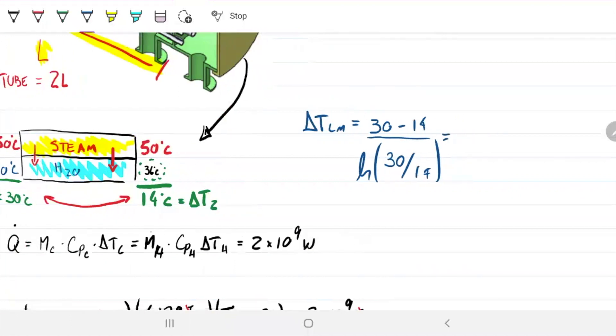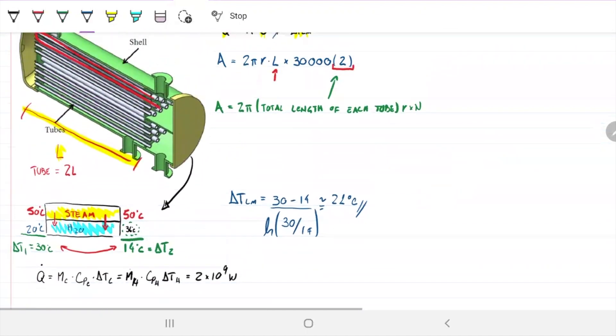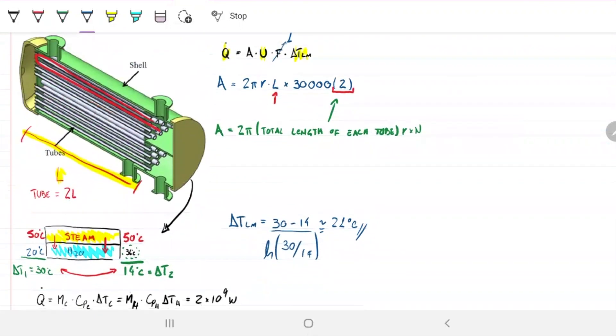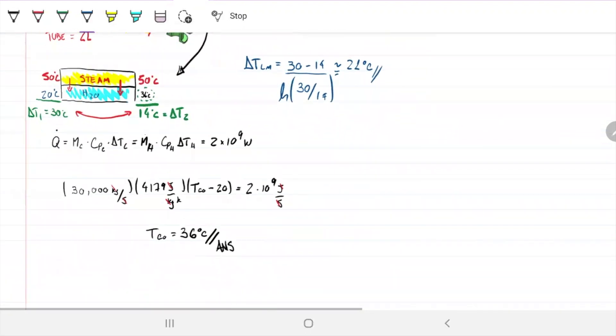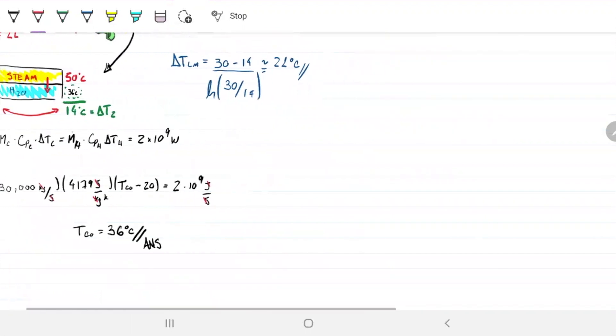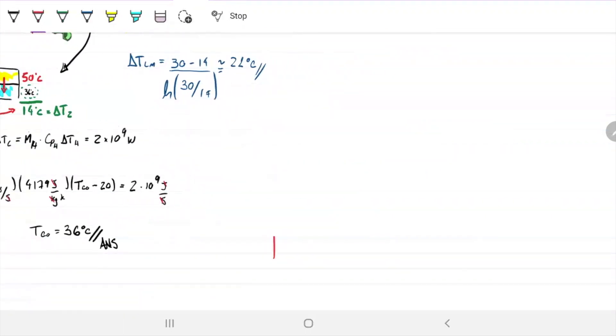If it were a simple mean, we'd have exactly the middle point on a linear scale. But since it's not linear, we're going to have something a bit smaller. Delta T log mean will be (30 minus 14) divided by the natural log of (30 divided by 14). This turns out to be about 21, or 20.99 something. So that's one of the things we needed to solve our top equation there.